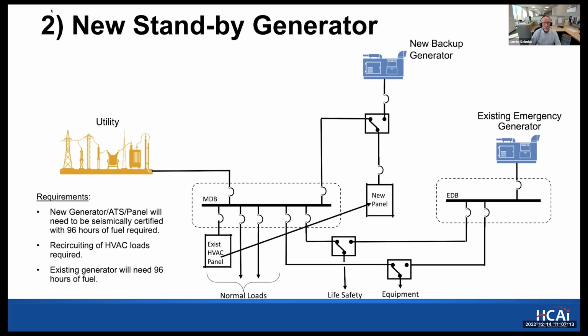The second solution is a dedicated new backup power source that would back up the existing HVAC equipment, transferred to this new panel. Again, this new source would need to have 96 hours. The existing generator would need to have 96 hours of fuel, and the new system as installed would need to be seismically compliant.